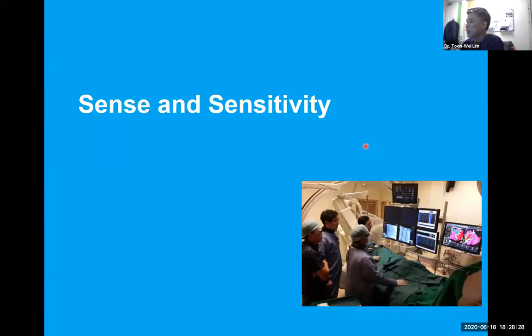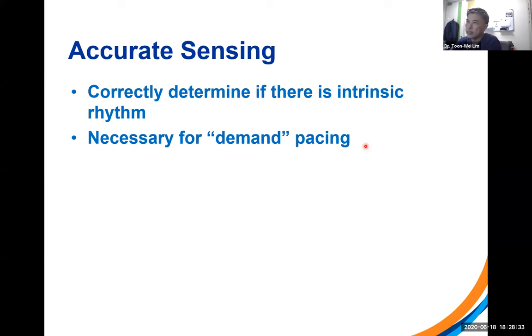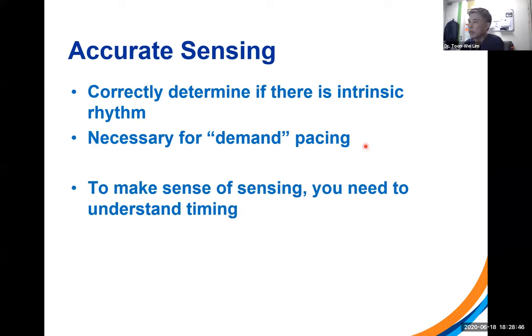So the next thing we'll talk about is sensing. The reason sensing is important for correct functioning of the pacemaker is that it helps you determine if there's intrinsic rhythm and is necessary for demand pacing, which is how nearly all pacemakers are set up these days. And to make sense of sensing, you actually need some understanding of timing as well. The reason for that is you need to know whether the pacemaker has sensed something correctly and reacted appropriately, or whether it's failed to sense an event and inappropriately responded.